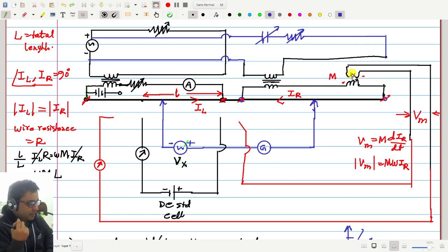That is the thing, right? Now, after you make one signal generator and calibrate it, if you find your signal generator is very robust and its properties are not changing with time, which you can ensure by calibrating it several times after several days at several different conditions, like different power supply fluctuation, and if you see that its displayed value and actual value are very similar, then you can use that as your standard.